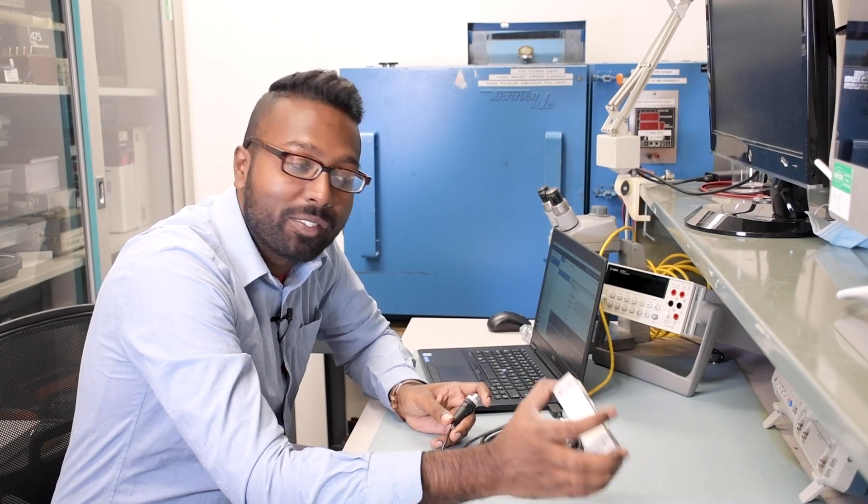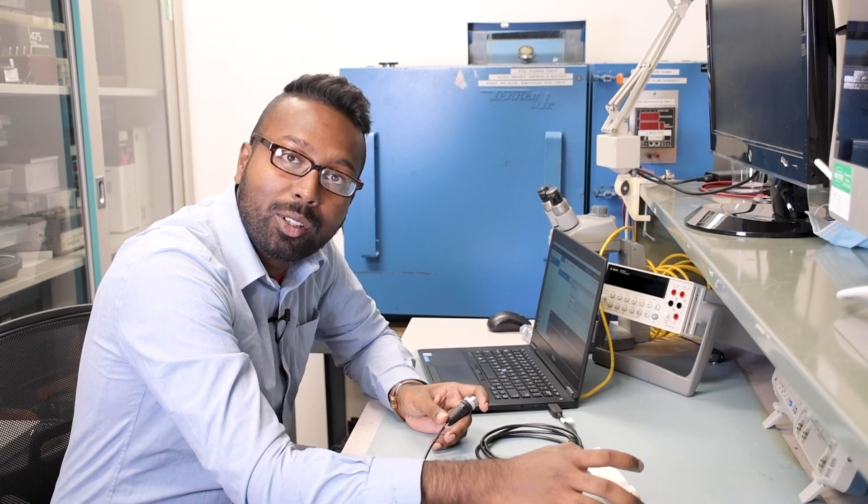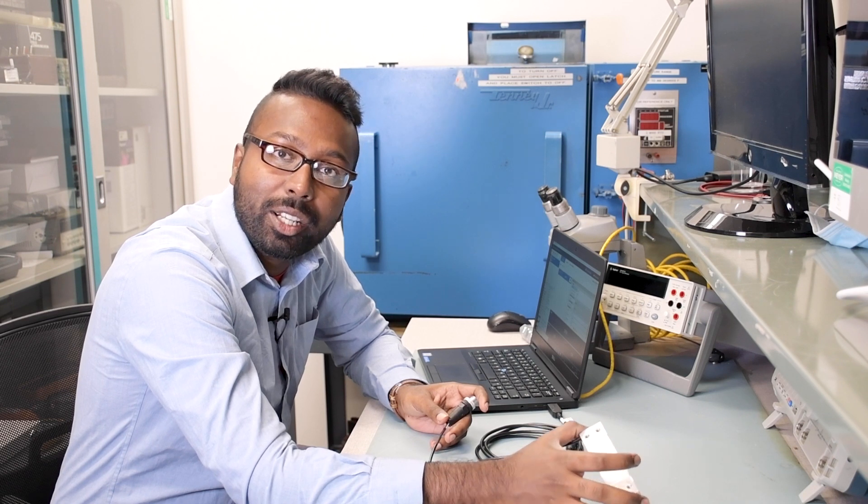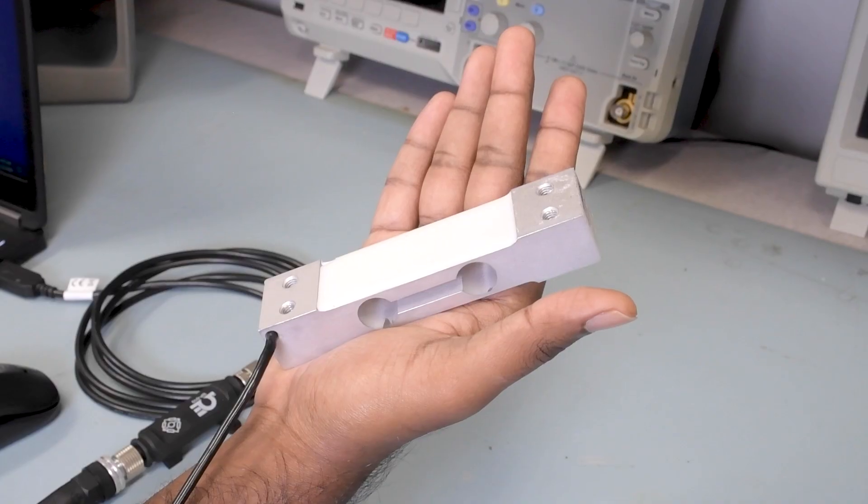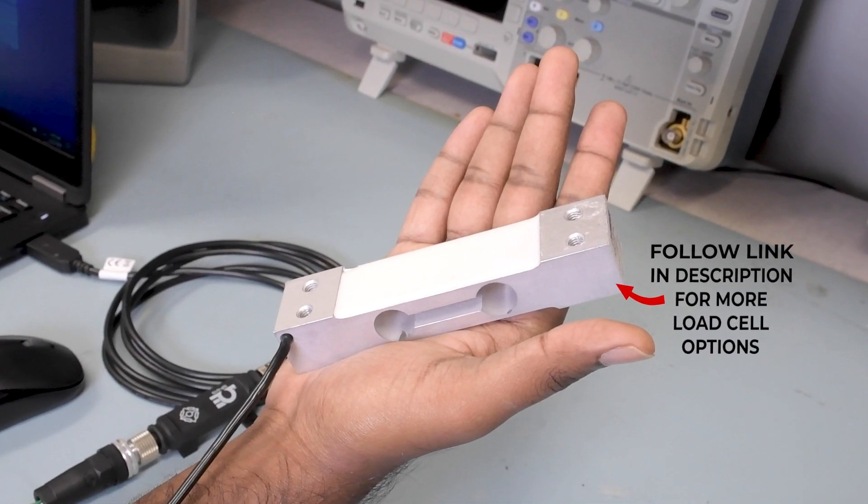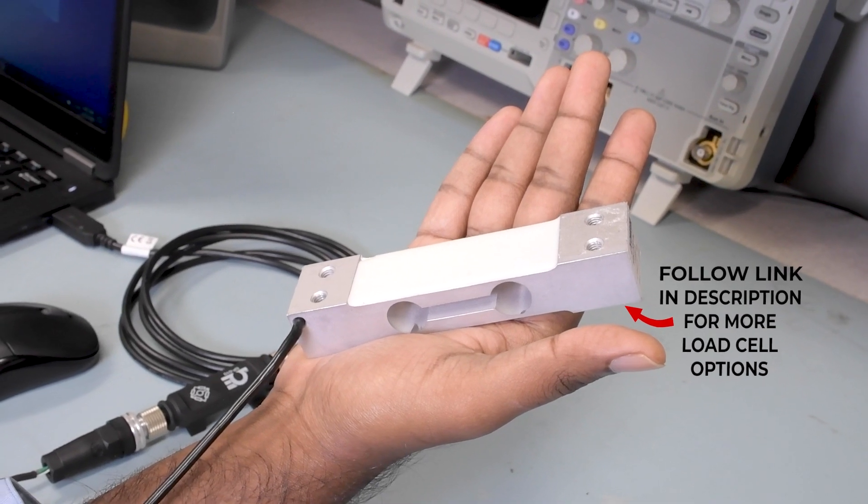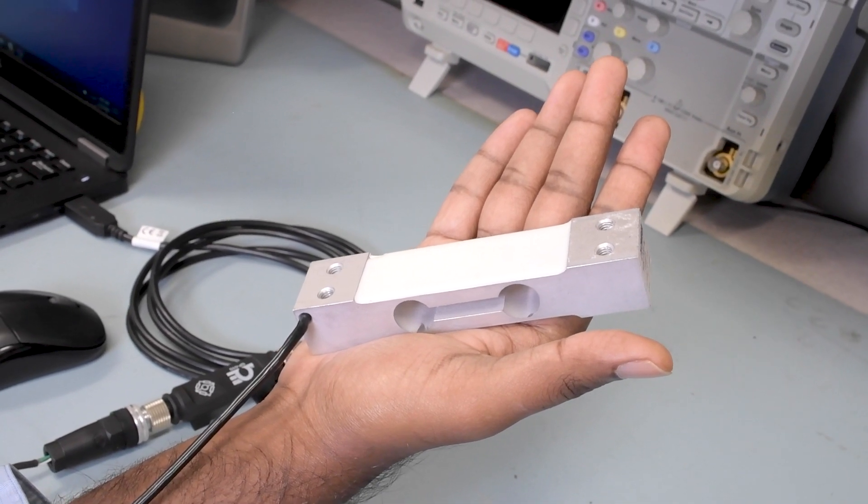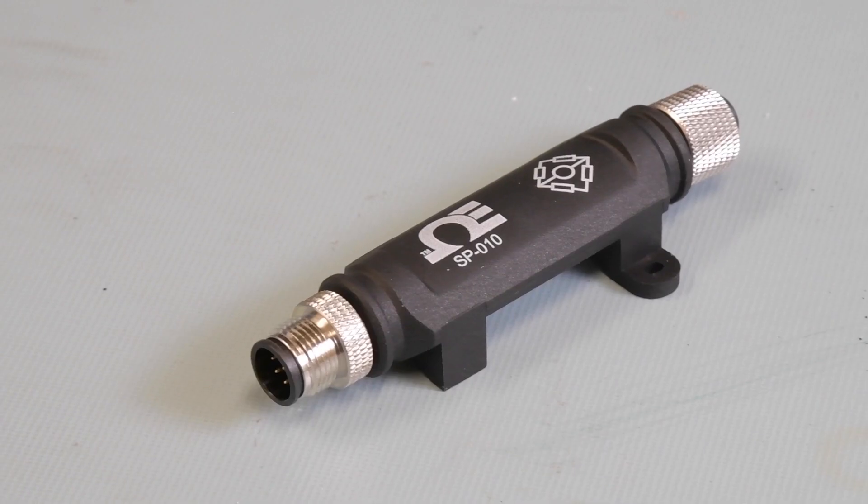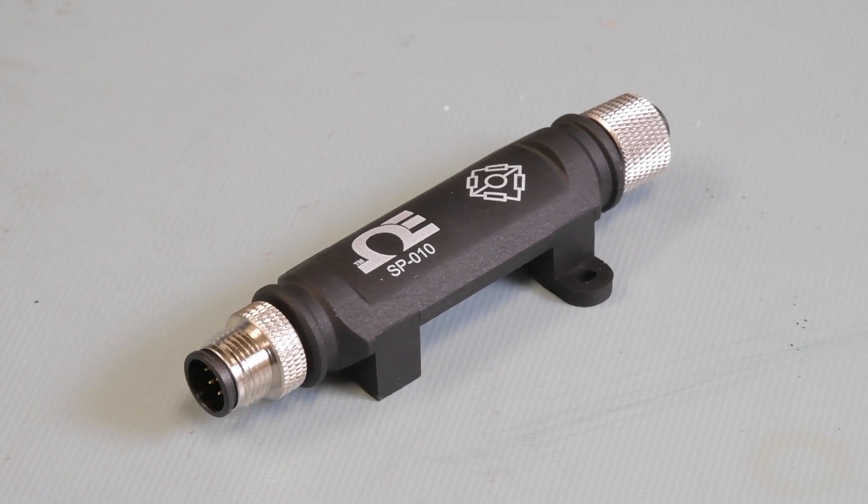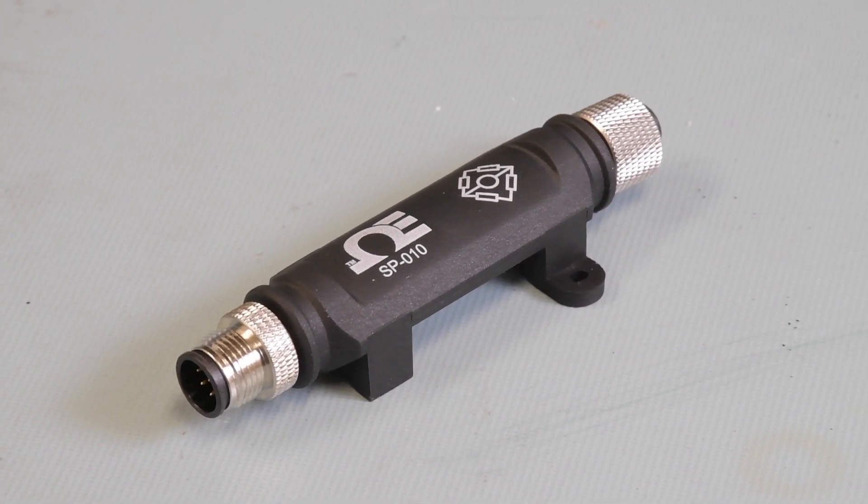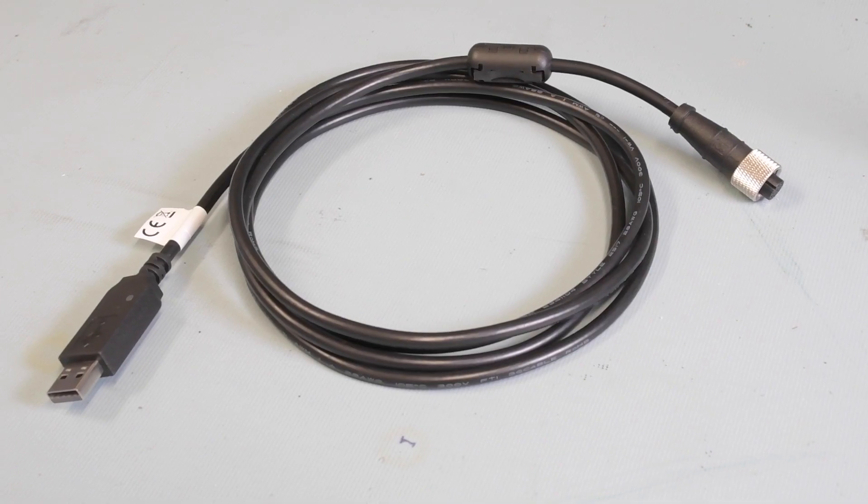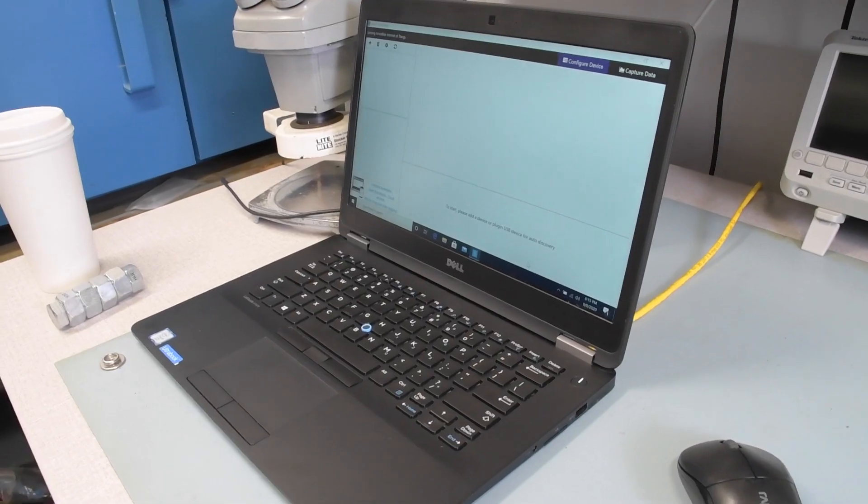The first step consists of connecting the load cell to the SP010 and calibrating it using the Omega Sync software. For this setup, all you'll need is a load cell with a ratiometric millivolt per volt output connected to an M12 receptacle. The M12 receptacle plugs into the SP010 smart sensing interface, and the interface connects to the USB serial communication cable that plugs into your computer.